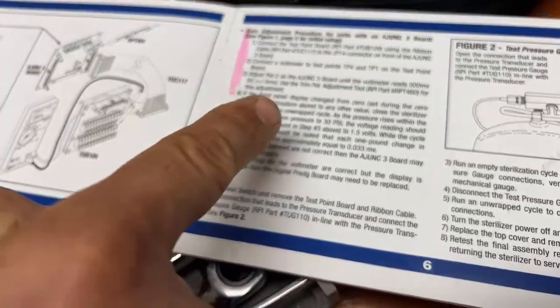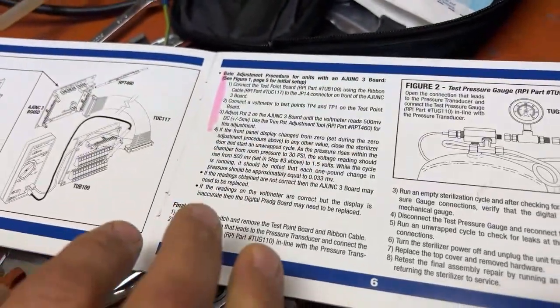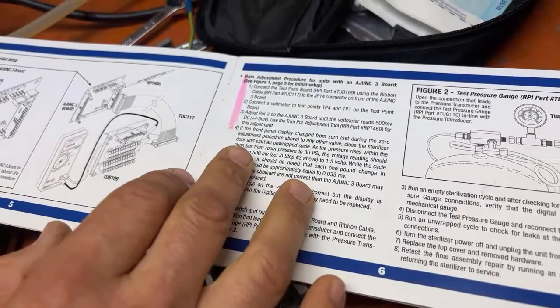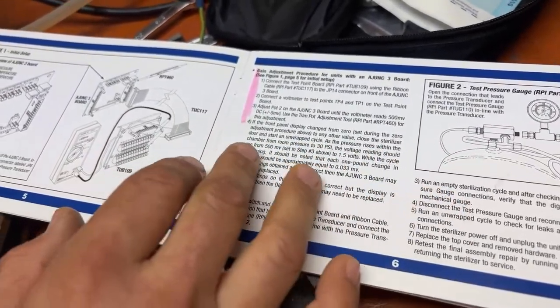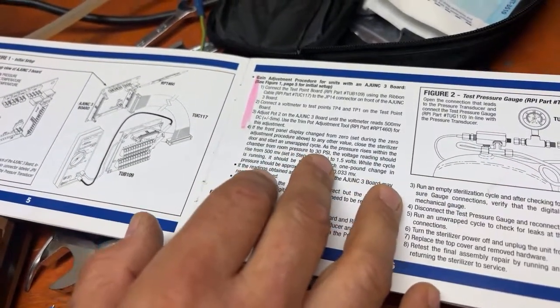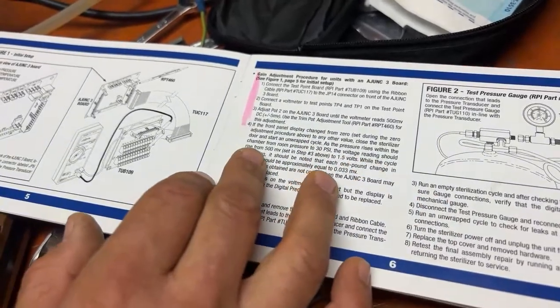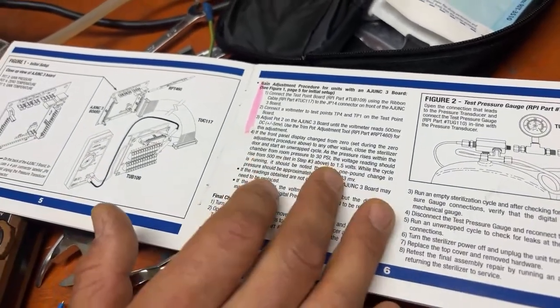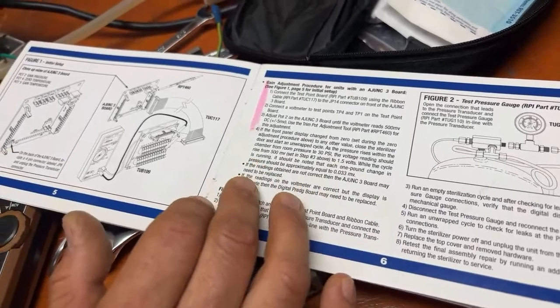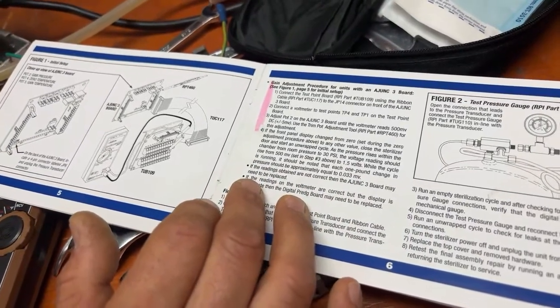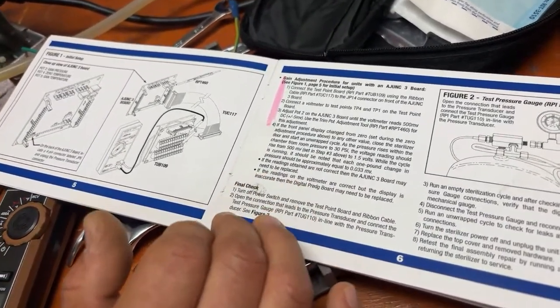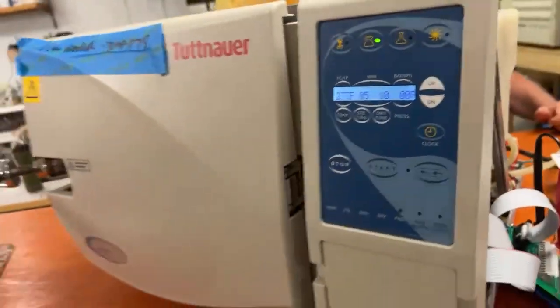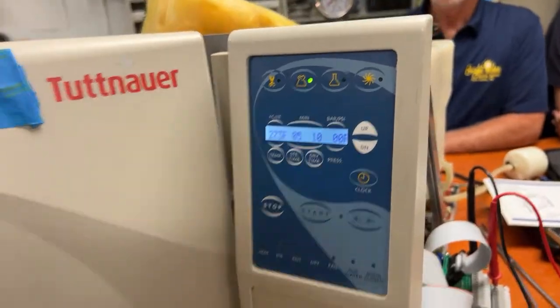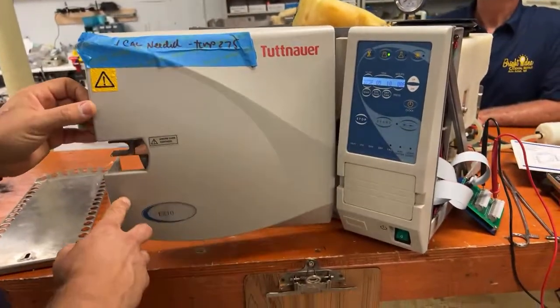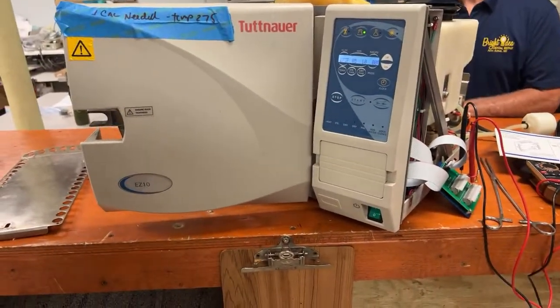All right, now, if the front panel display changes from 0, close the sterilizer door, start an unwrap cycle. If the pressure rises within the chamber to 30 psi, the voltage reading should rise from 500 millivolts to 1.5 volts. Okay. So let's go ahead and see what our pressure is here. All right, so we're at 0 psi. So at this point, we're going to go ahead and we'll put a tray in.